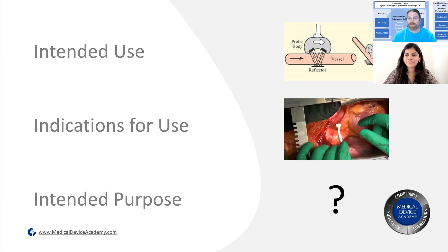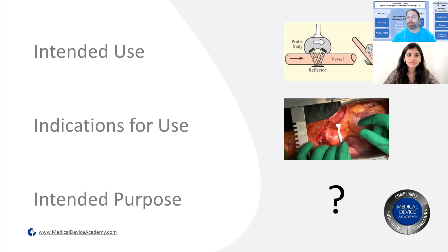In this slide we have two different images. The top image shows how you would measure flow of liquids through any kind of vessel — whether it's tubing, an artery, or a vein. That's actually how they measure blood flow in surgery, and also for hemodialysis, but they also use it in industry. If you're trying to measure flow of gasoline or some liquid through a pipe, this is how non-invasively — without putting a probe into the pipe — they can measure the flow through it, using ultrasonics and calculations.